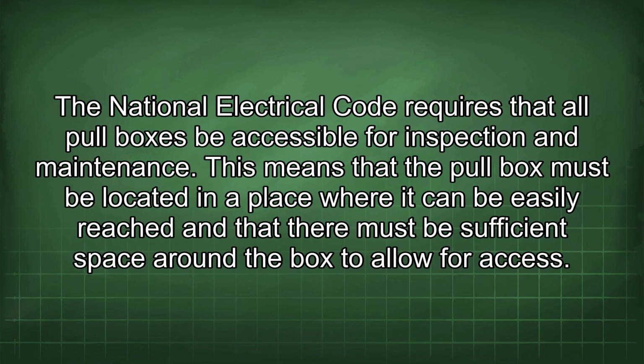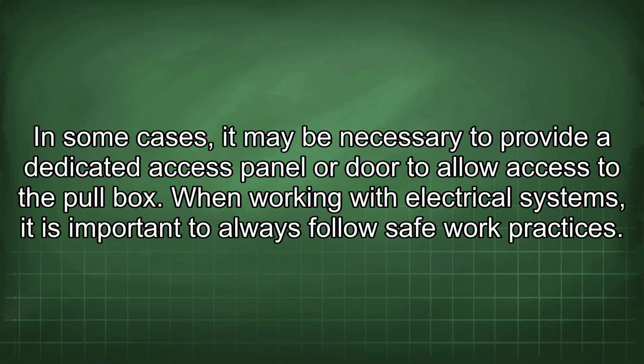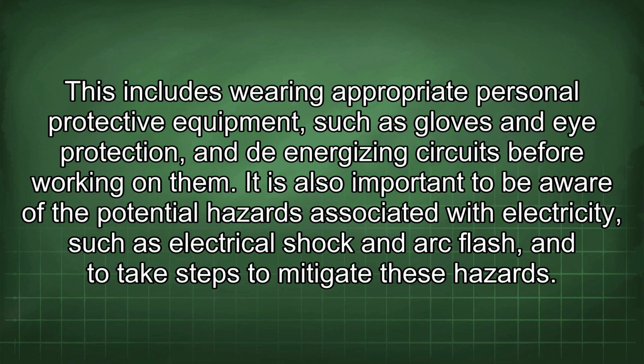The National Electrical Code requires that all pull boxes be accessible for inspection and maintenance. This means that the pull box must be located in a place where it can be easily reached and that there must be sufficient space around the box to allow for access. In some cases, it may be necessary to provide a dedicated access panel or door to allow access to the pull box. When working with electrical systems, it is important to always follow safe work practices. This includes wearing appropriate personal protective equipment, such as gloves and eye protection, and de-energizing circuits before working on them. It is also important to be aware of the potential hazards associated with electricity, such as electrical shock and arc flash, and to take steps to mitigate these hazards.